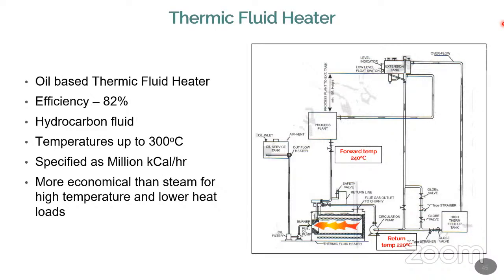Then there is no need for a flue gas analyzer or flue gas chimney. Even though a flue gas system is available, it is not in a very big way. Similarly, you do not have a condensate recovery system, steam traps, functioning of steam traps, or flash steam vent. Those things are completely not required for this system. We need only the energy content that can be used with the help of a TFH. It is more economical than steam for high temperature and similarly for low heat load applications.